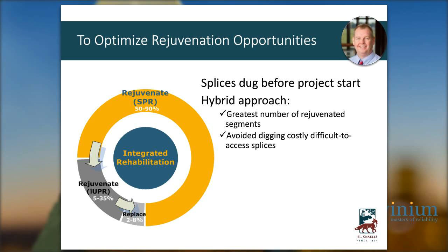In the event that you have a difficult to access splice, but it will flow fluid, by being flexible and accepting the unsustained process, which again takes that second trip, you get the cable rejuvenated at a lesser cost than traditional directional boring, and you don't have to dig that splice.